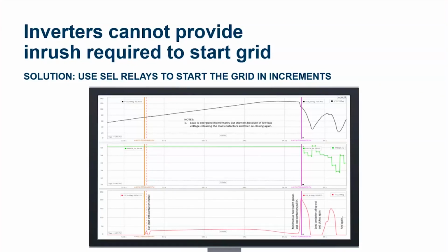That's okay. You have to, by the way, separate the inverter to allow it to ramp this, so you can't have your loads attached to this grid. So how do you do that? You use a relay to isolate your loads from your inverter, right? And then even further, what you can see here is even when the load started, you saw the contact chatter as the voltage bounced in and out as you hit the current limit of said inverter.